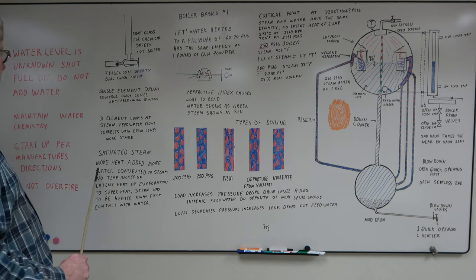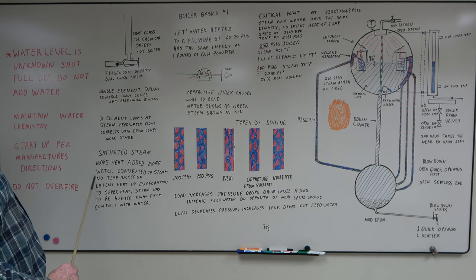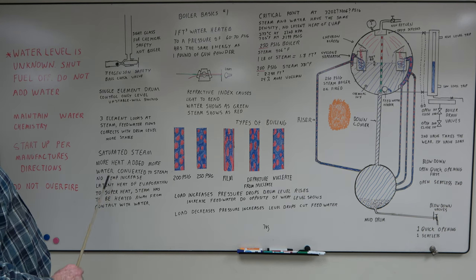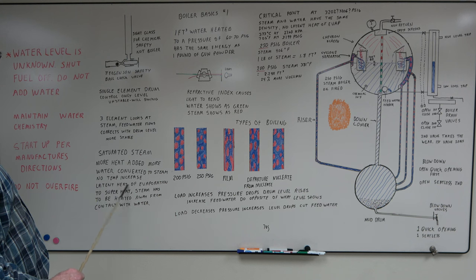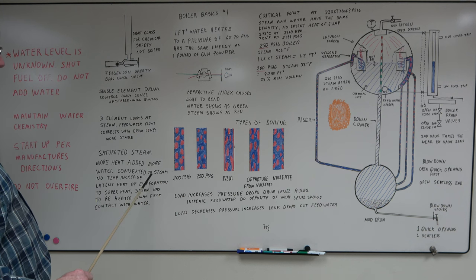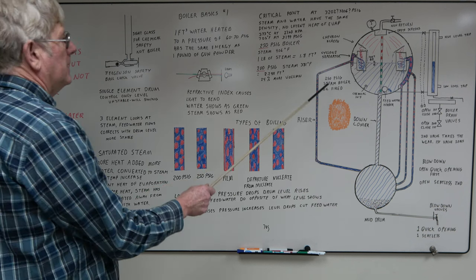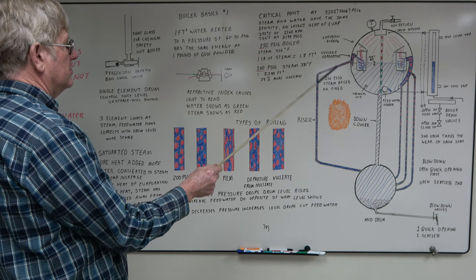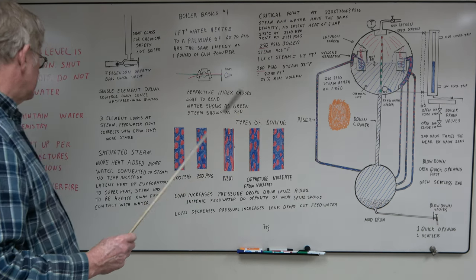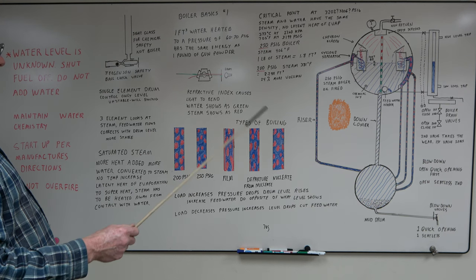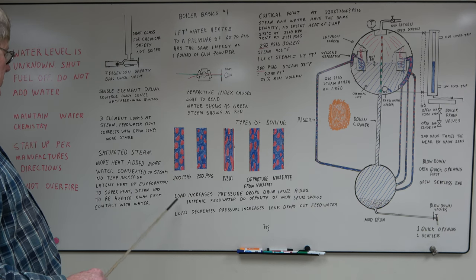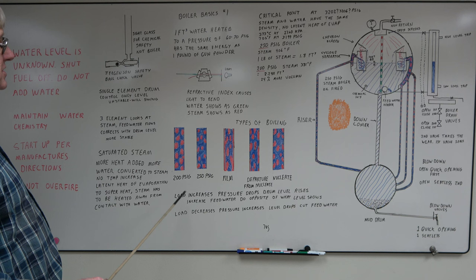The saturated steam, the more heat added, more water is converted to steam. There's no temperature increase. It's a latent heat of evaporation. So if you fire this harder and the pressure stays at 250, you're just going to make more steam. The temperature will still be 406 degrees. The only way to superheat is to get the steam away from the water. Then you can add more heat to the steam that way.